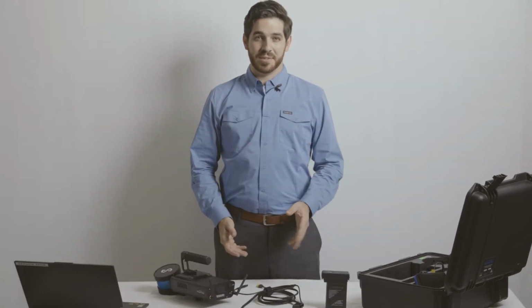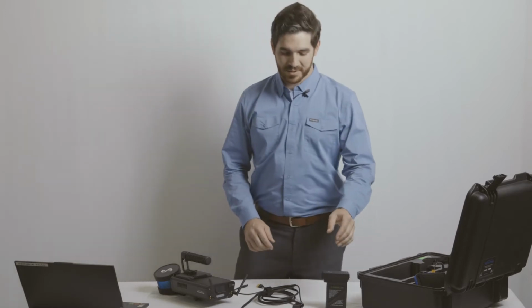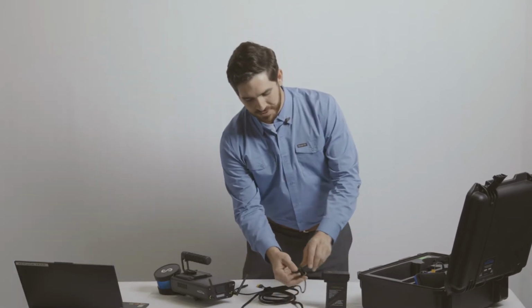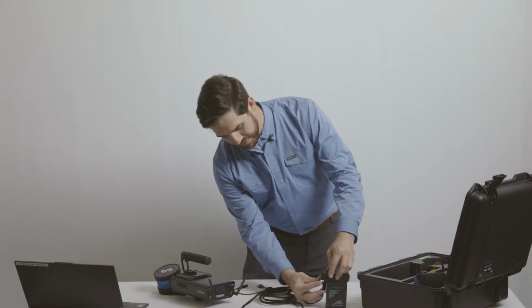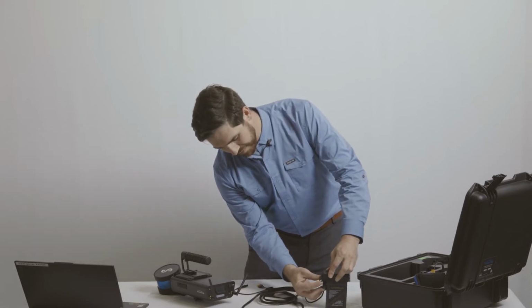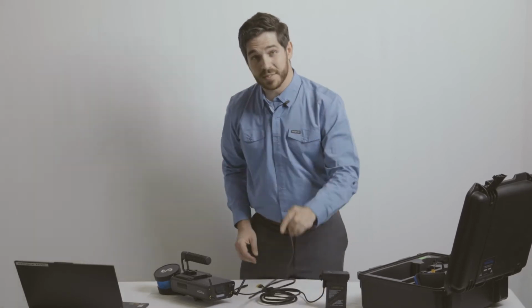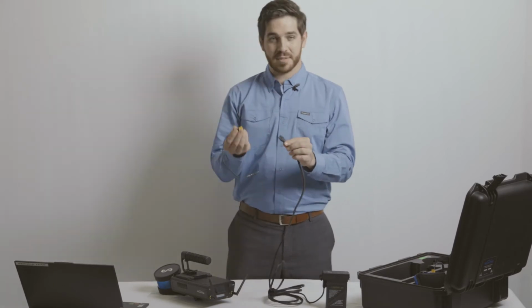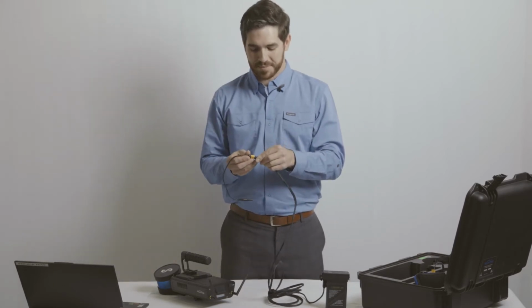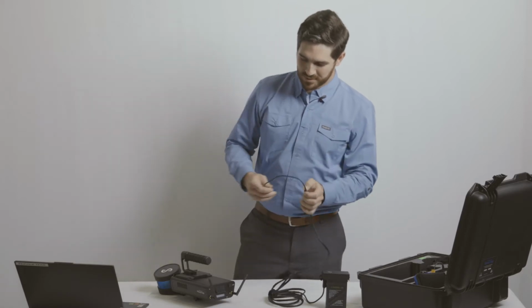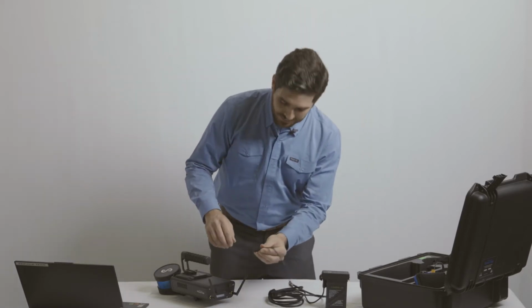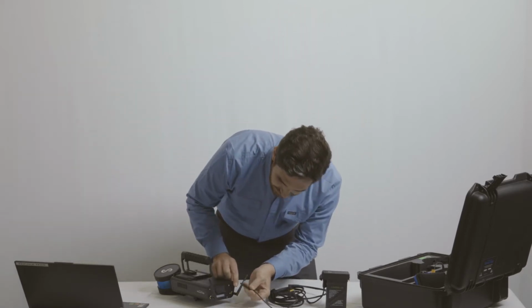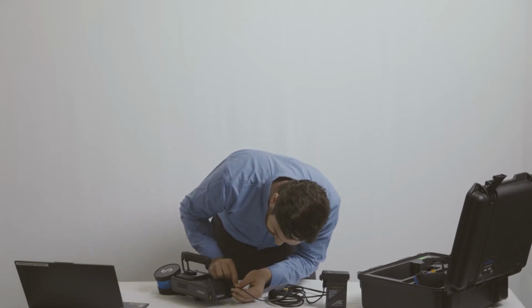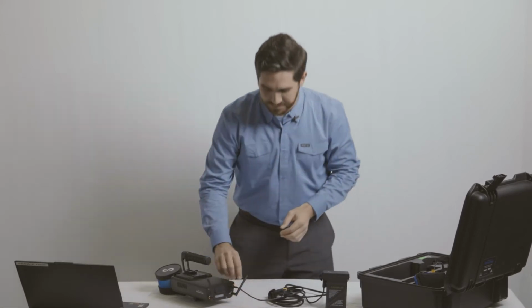Now that we've verified everything has arrived safely, let's go ahead and power up the unit to test it. Plug your 2-pin TB47S adapter into your TB47S battery. Then take the XT60 end and plug it into your XT60 to 2-pin Lemo adapter. Next, we want to plug the 2-pin Lemo into the back of the Hovermap unit. Be sure to line up the red dot on the connector with the red dot on the port.